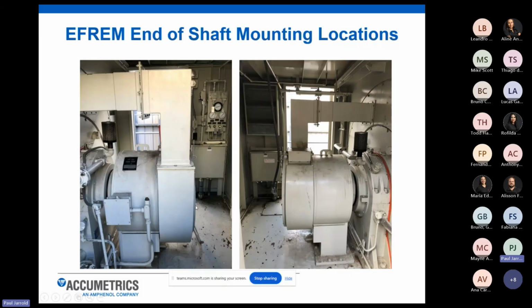And the end of the machine just has a cover plate, and the field winding leads come all the way through the generator rotor and directly into the brushless exciter rotor. And then there's an access point to get to those leads on the end of the machine. So this is a more simplified design. This is more common in your GE style LM6000s, LM2500 style gas turbine generator sets that are maybe 40, 50 megawatts up to 180 megawatts or 200 megawatts, something like that in size. So smaller than the mid-shaft application.